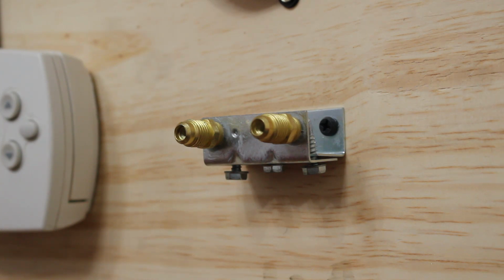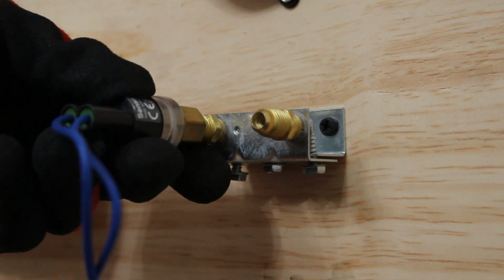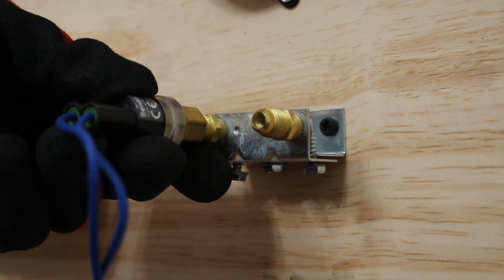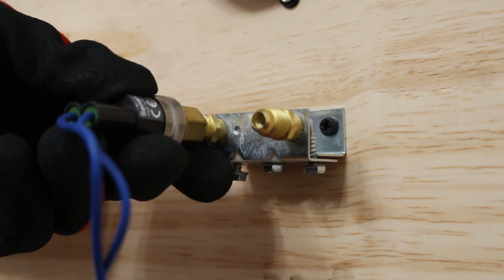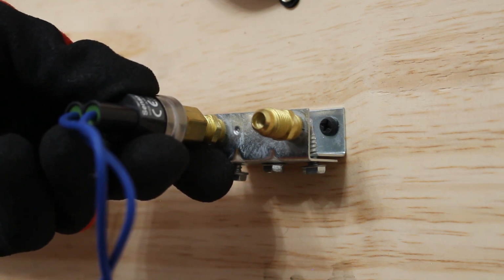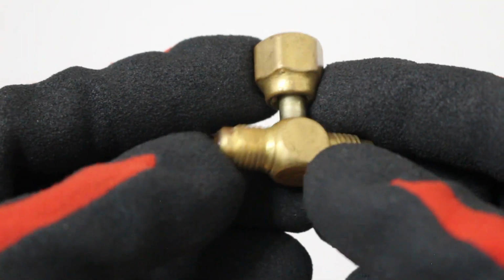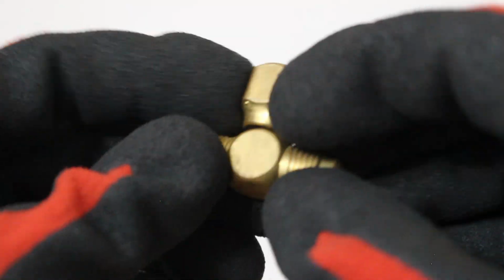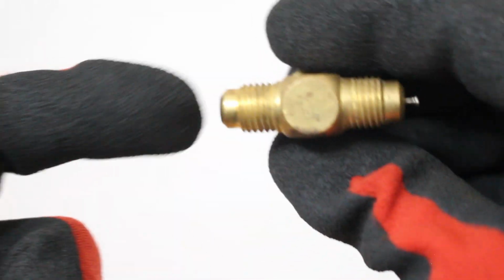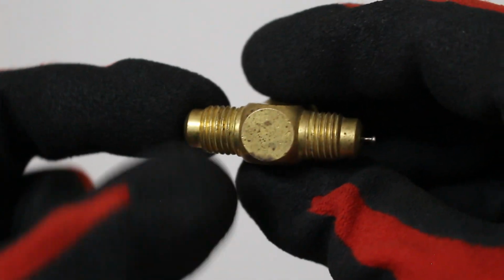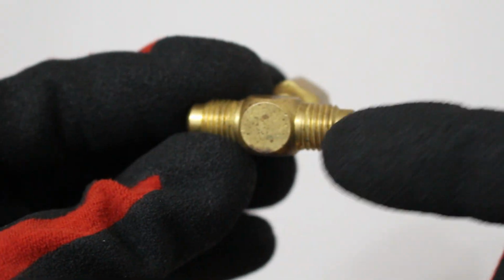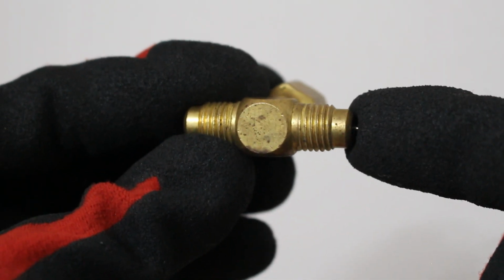So one key step I do want to point out is that you do not want to install your pressure control just like that. Let's say this is our only low pressure port. From here, yes, we might install the control, but now we have nowhere to test pressures. In that case, you're going to want to install a swivel T. This is a swivel T. So we would connect this port onto our pressure port. And now we have one side where we can connect our pressure control. And at the same time, we now have an access port to check pressures.